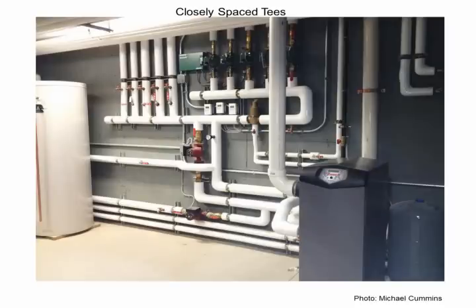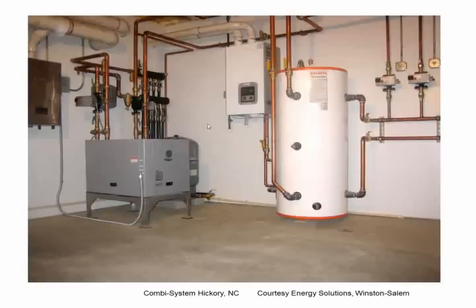Now, I didn't get a chance to talk to Michael Cummins here, but I really like this job that I found. I like it even though it doesn't have a stick of Caleffi on it. It's very good, but it's also a good place to talk about closely spaced tees. So here's his primary loop, and he's using closely spaced tees right here. And what he's done is follow the rule of making sure your tees don't exceed 4 times the pipe diameter of your pipe. If instead of connecting here, he decided to connect here, that spread would cause these pumps to interfere with one another. So keep them close together.